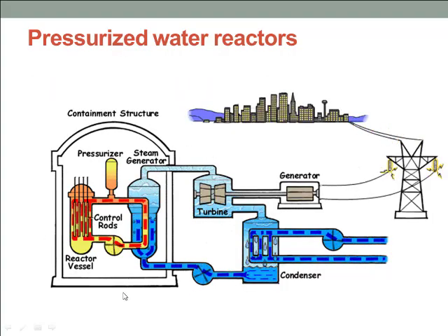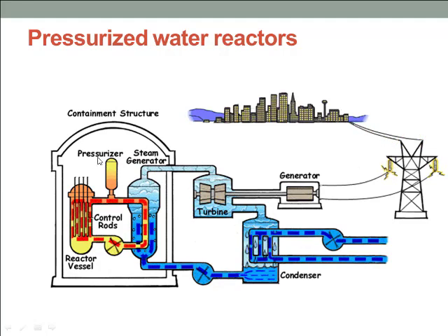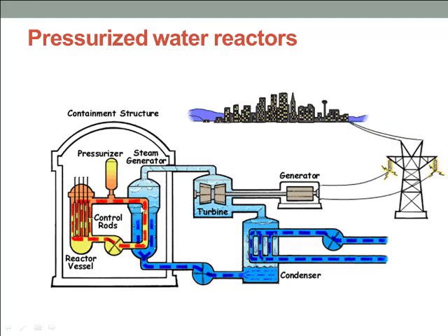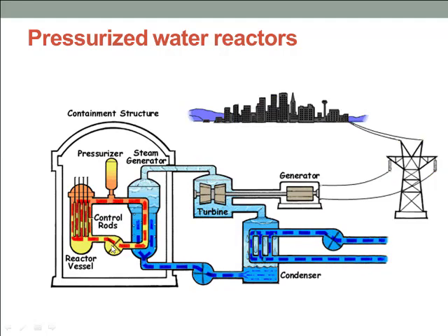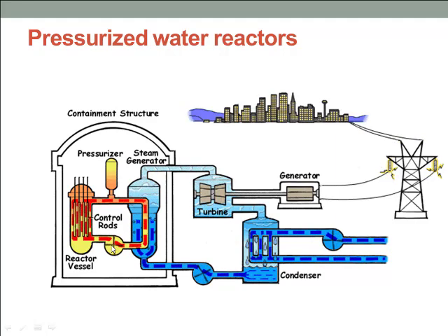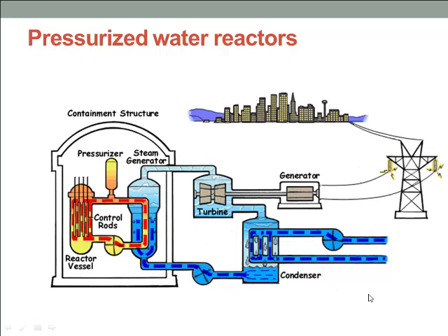The rest of the construction of the pressurized water reactor is the same as the boiling water reactor. The difference lies only in this part, where you can see a pressurizer is installed, and the core of the reactor is separated from the circulating water. In this part, the water heats up to 588 Kelvin under high pressure conditions, which does not allow it to boil. This hot water then exchanges heat with a lower pressure water system which turns to steam and drives the turbine. Now we shall discuss the components of the pressurized water reactor one by one.